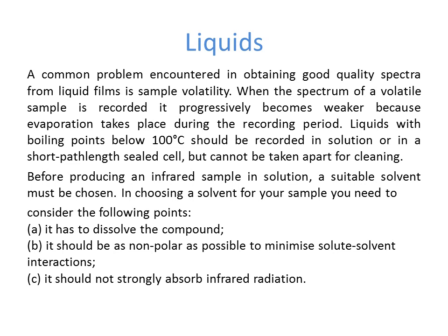But these sealed cells are very difficult to clean, because they cannot be dismantled. When you take the solvent into consideration, the properties that should ideally be exhibited by the solvent are: it should dissolve the compound, it should be miscible with your analyte, it should be non-polar so that you can minimize the solute and solvent interaction, and it should not strongly absorb infrared radiation.